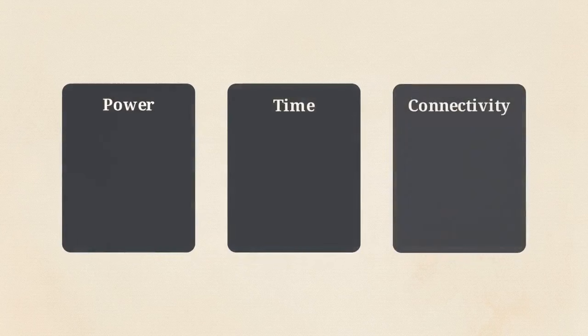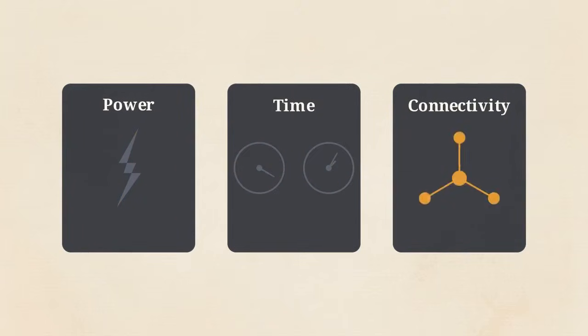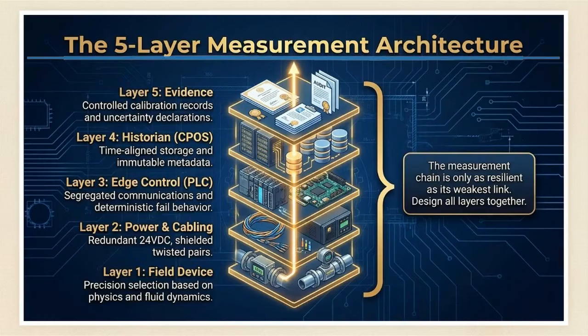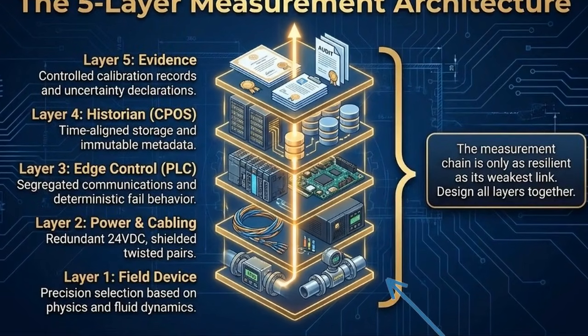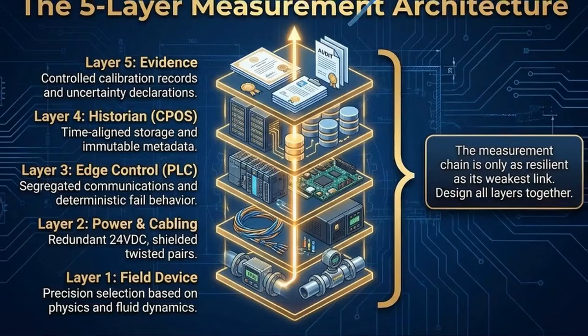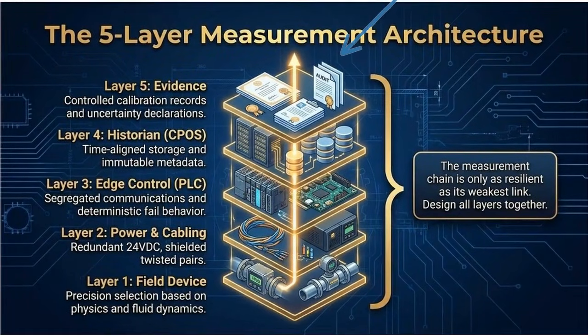High-accuracy field sensors are useless if their support infrastructure fails. A precision instrument cannot compensate for dirty power, mismatched time synchronization, or a broken network connection. This diagram shows the 5-layer measurement architecture. True precision requires building a unified system that starts down at the physical field device and extends upward through power, edge control, and the historian, culminating in the final evidence pack.